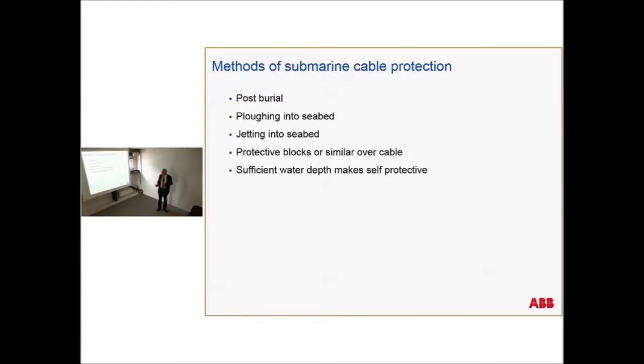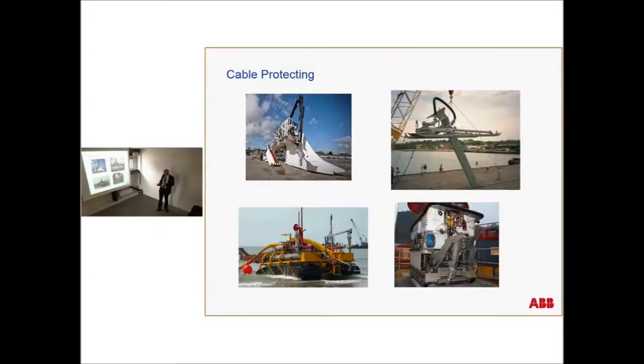You can do plowing if it's soft, or jetting, or if you can't do it, maybe you have to put blocks or mats over the cable. In very deep water, I think below 1,500 meters, you normally don't have to protect the cable because there are normally no activities at that depth. Some small pictures from different equipment used. Plow, you see along plow as well.